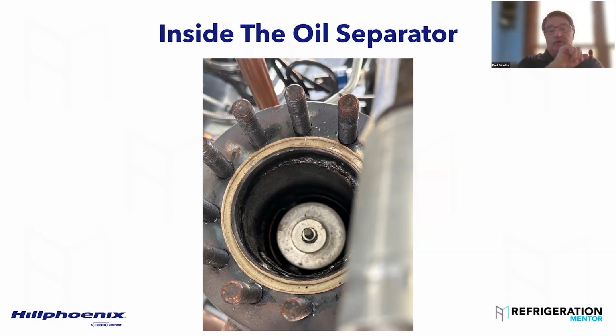So what we're going to do is isolate the vent to the receiver, the vent to the flash tank, or the DOS solenoid supply line, and leave open the isolation valve to the compressors, and we're going to pressurize that oil receiver to 300 pounds. This is the only point in time I'll tell you to use a regulator. That way it's easy to maintain our 300 pounds and we can fill up our compressors. I'll turn on number one. I want to see it fill. I want to watch it go up and I want to watch it stop.